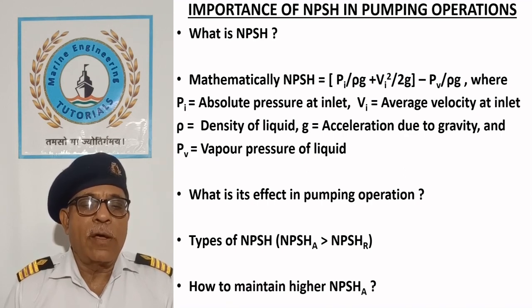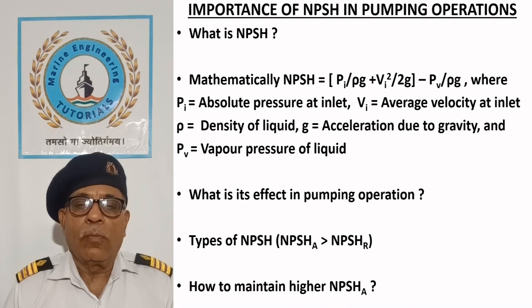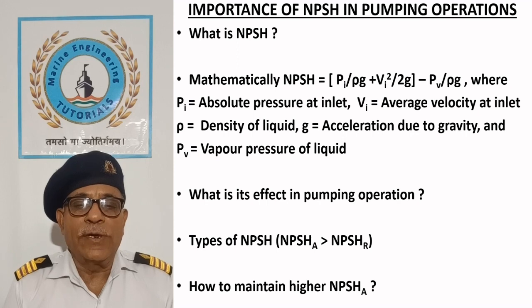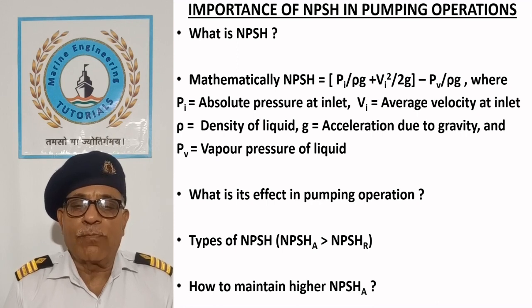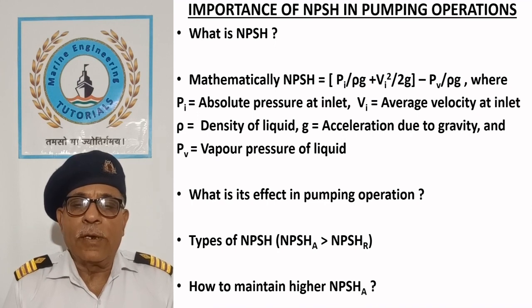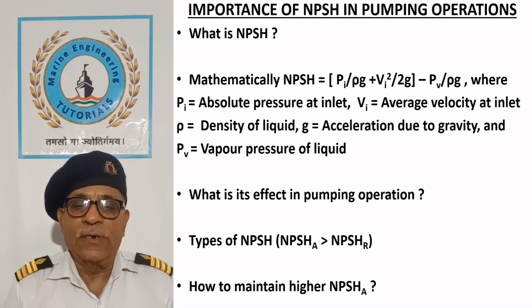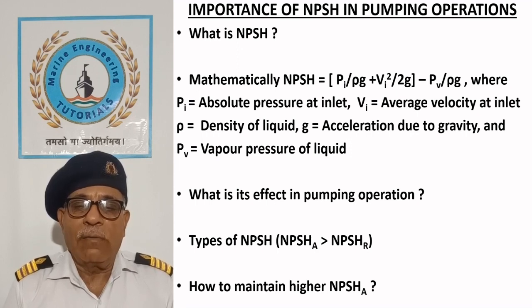How to maintain higher Net Positive Suction Head Available: As discussed in lecture 1, some head is lost due to major and minor losses on the suction side. To reduce these losses or to increase NPSHA, the pump should be placed closer to the liquid to reduce suction pipe length. The suction pipe or pump is usually larger in diameter than the delivery pipe to reduce head loss. Straight pipes with minimum fittings such as valves, bends, tees, and filters should be considered. A gate or butterfly valve should be used, which offers minimum resistance with full flow characteristics.